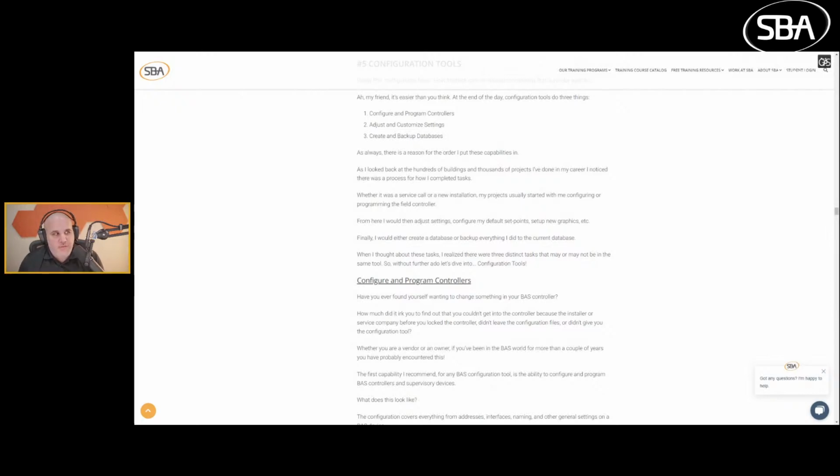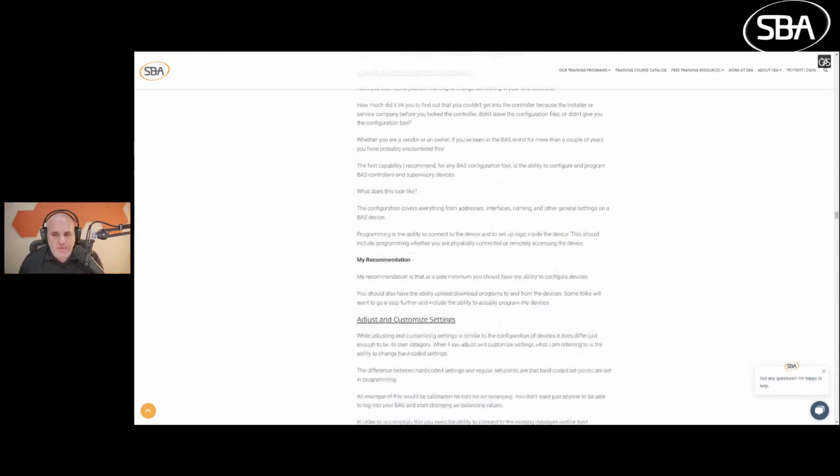I'm telling you, if you don't get that in and you don't make sure that you do have that prior to project closeout, then you're going to find yourself in a situation where you may have systems that are vendor locked. You may have systems where you don't have the programming files. You don't have the setting files. And anytime you need to make a change, you don't have the software and you don't have the programming files from which to base those changes on. So I really recommend you build that in.